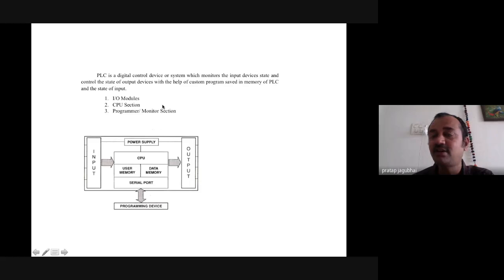So the PLC is a combination of input output modules, which are the interface to the process, then the CPU, which is the controller, comprising the communication port as well as program memory, data memory, and the power supply, and the programming devices like a keyboard or a monitor, where you can see the output parameters, or you can see the set point entry, or you can give the entry and download the program to the controller also.